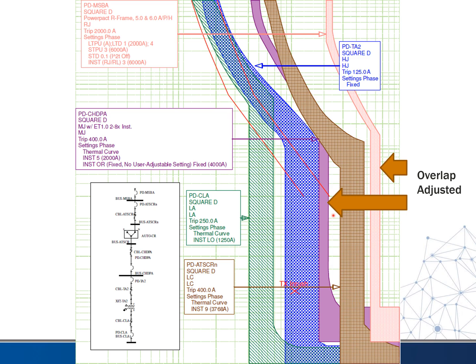How exactly do we do that? You see in these boxes all the different settings you have for the different breakers. For this first one, the STPU — short time pickup — was set to five. When I adjusted it to three, that slid this curve out of the way of the other breakers. Similarly, I adjusted the instantaneous setting on the other breaker and that moved its curve over. This isn't perfectly coordinated, but it's definitely much better coordinated than before. That's the purpose of these types of studies.